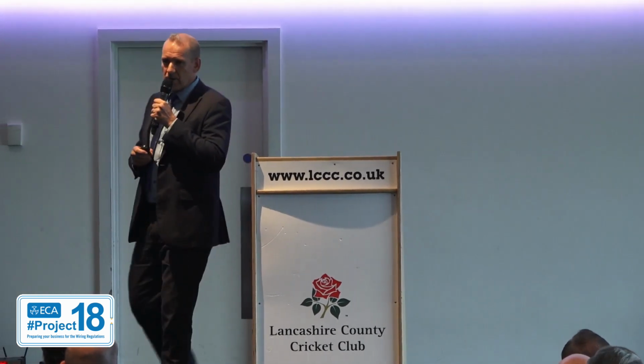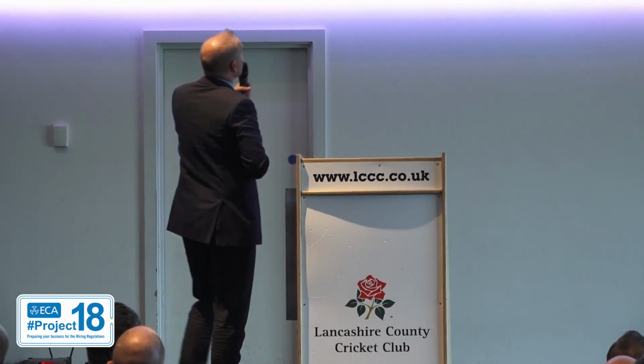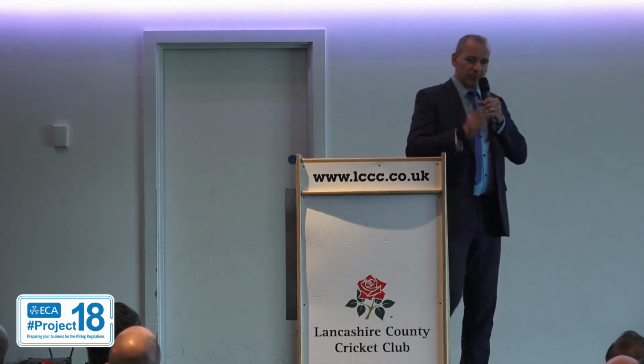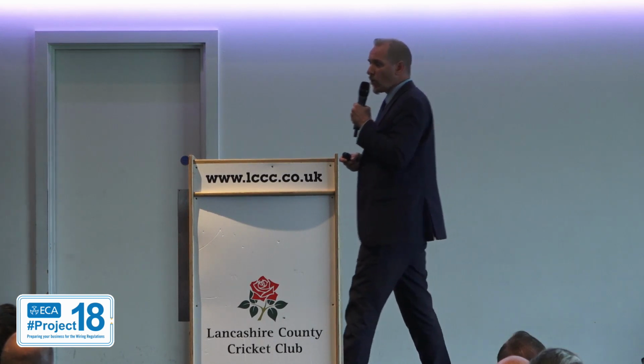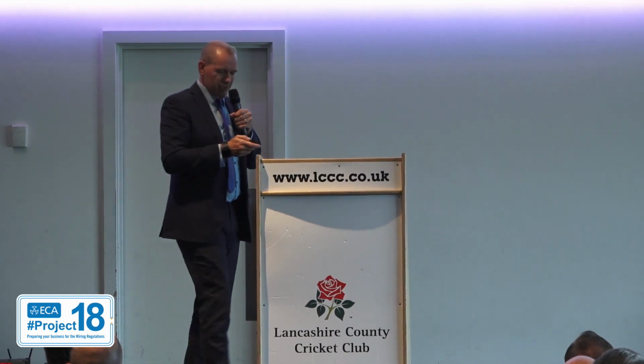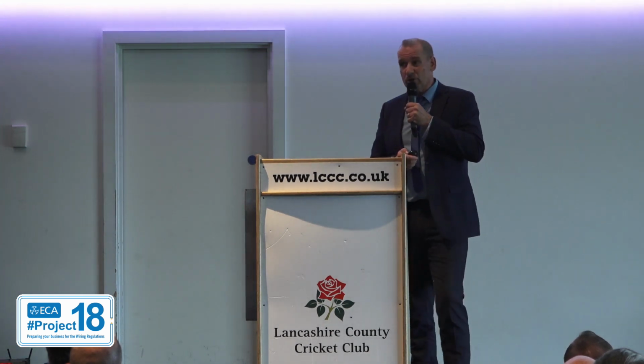Okay, so we go back to the diagram that I nicked off the internet. I put the green lines on myself, but I nicked the diagram. So here we have the designated escape routes indicated in the 17th edition that have a rigorous cabling requirement. All of the other zones around there have a less rigorous cabling requirement. So cables might be clipped up, they might be laying across grids, whatever they might be, but it's a less rigorous cabling requirement. In the event of a fire, and my example here shows that our escape route is no longer operational because there's a fire condition in the building.